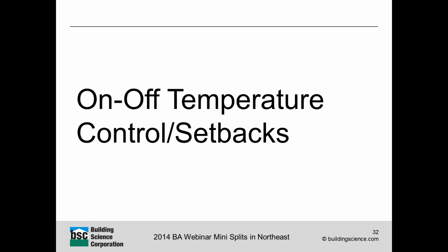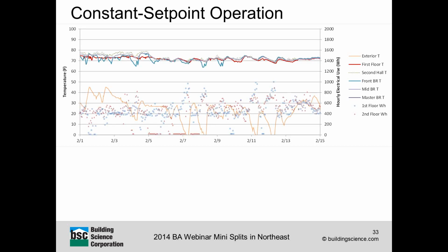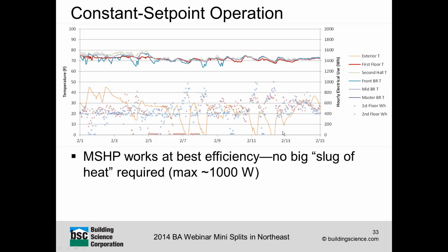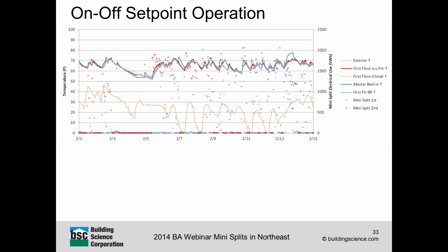So first, as an example, I'm showing a house that ran the temperature at a constant set point, just straight flat temperature. Once again, outdoor temperature in orange, indoor temperatures, and mini-split energy use. You can see the temperatures are pretty close within a reasonable band, and the mini-split is modulating up and down. Compared to the 2,000 watt peak load, we peak out at about 1,000 watts. So there's no big slug of heat, and this single point distribution works very well with this constant set point.